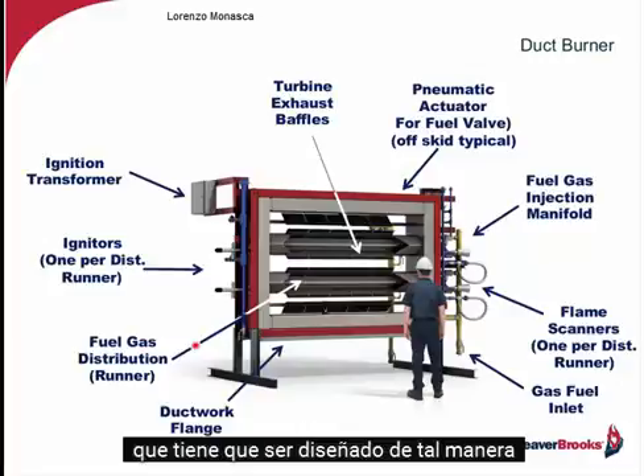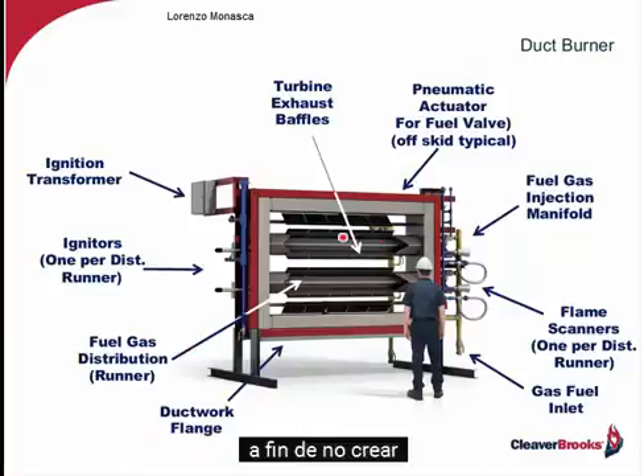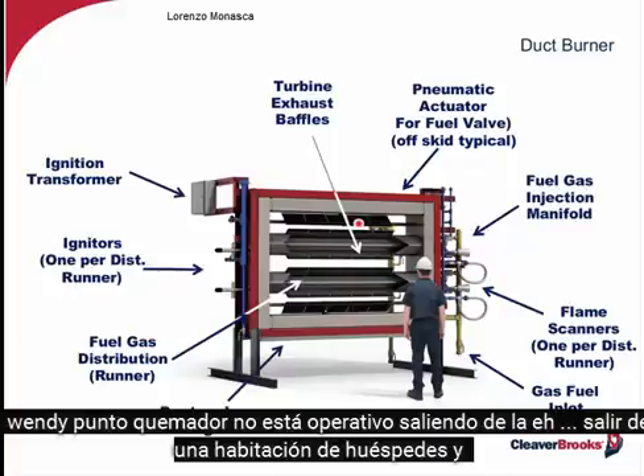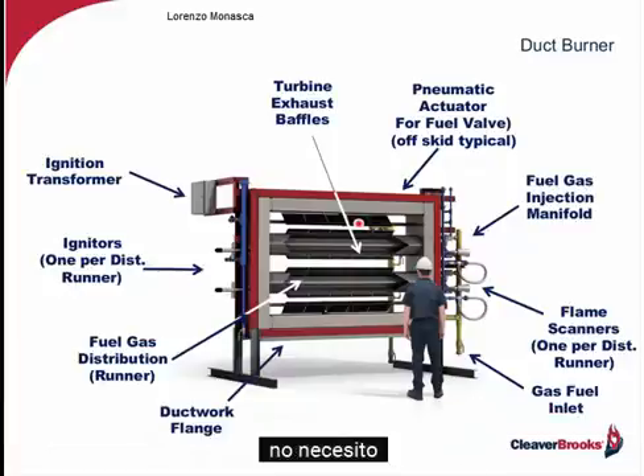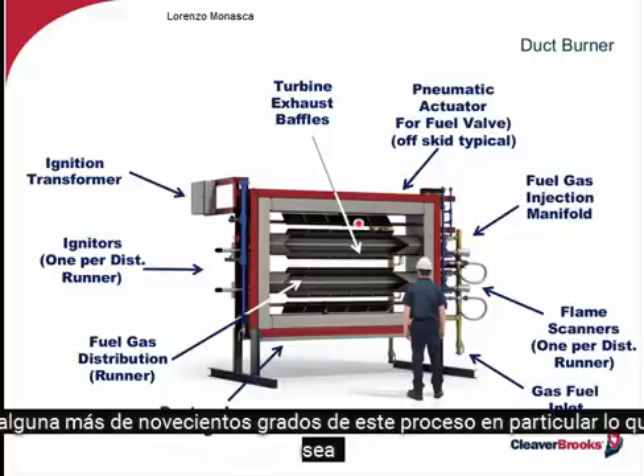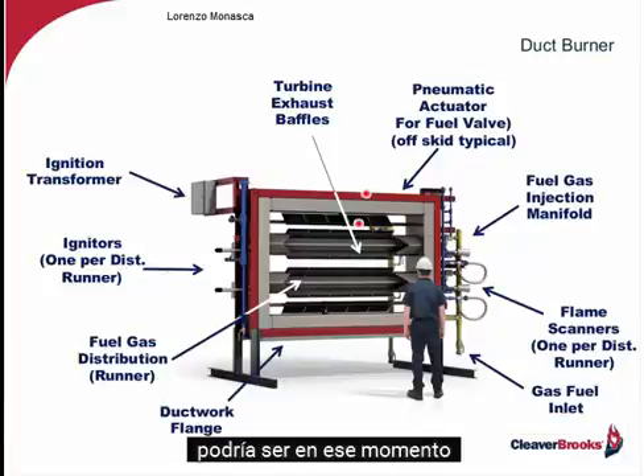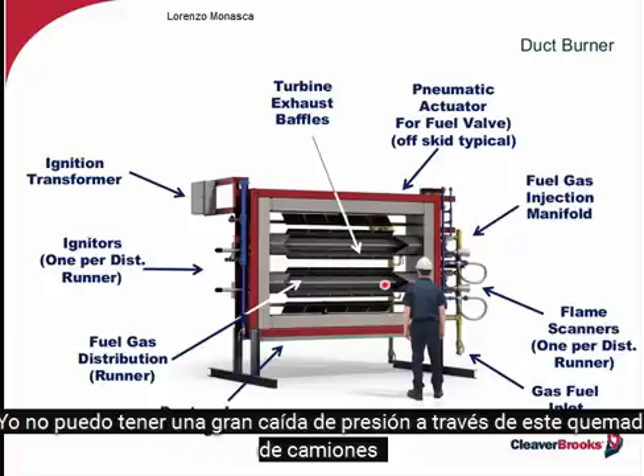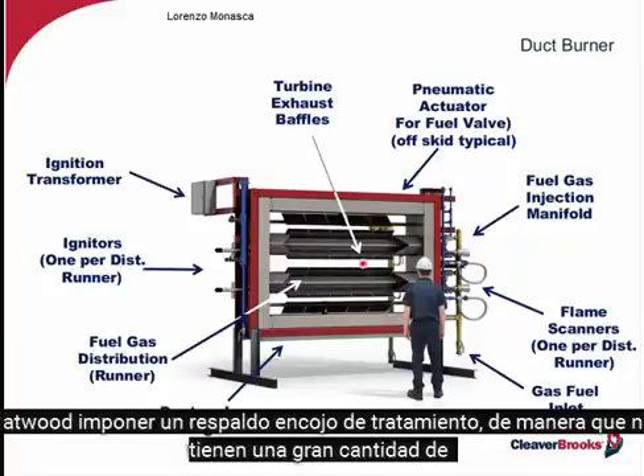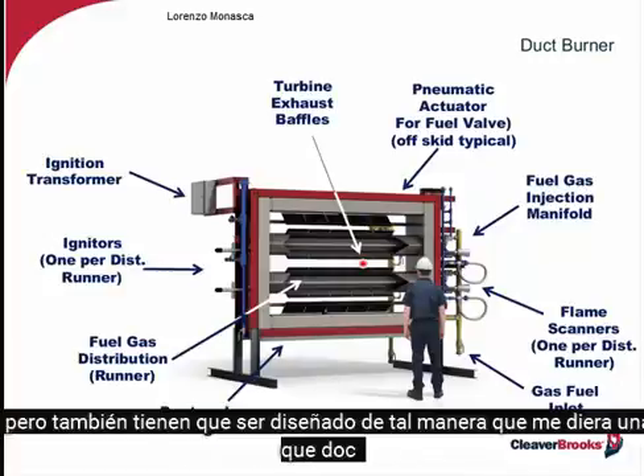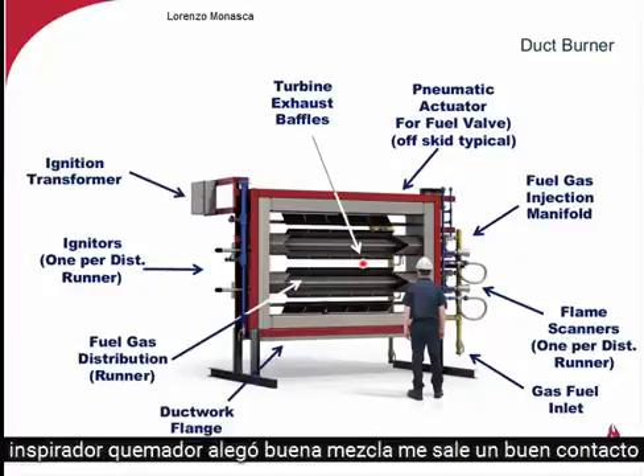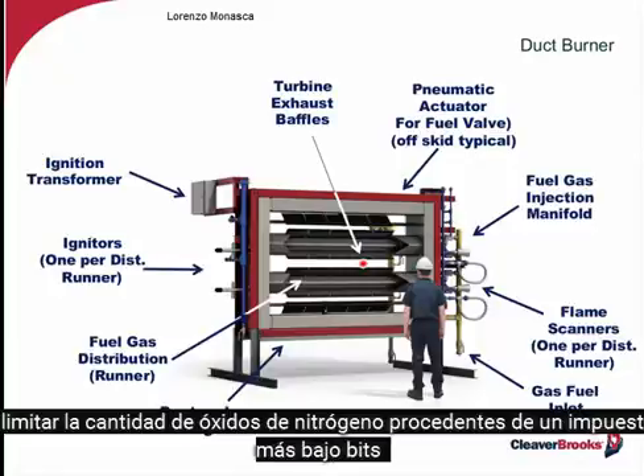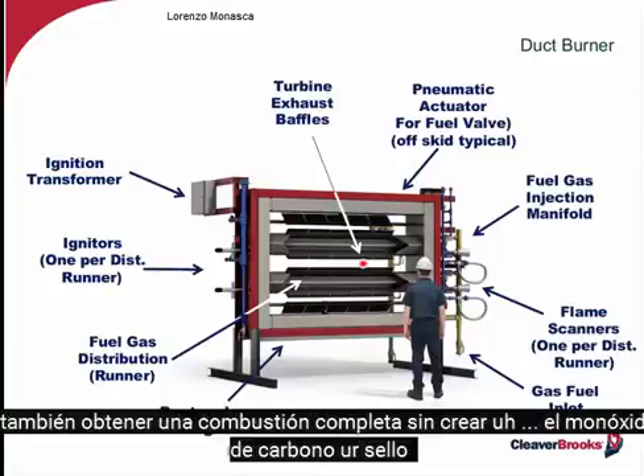Now, they've got to be designed in such a way so as not to create, when the duct burner is not operating, I'm coming out of the gas turbine, I don't need any more than 900 degrees for this particular process, whatever it might be at that point. I can't have a large pressure drop across this duct burner that would impose a back pressure on my turbine. So they've got to have a lot of open area. But they also have to be designed in such a way to give me, when that duct burner is firing, good mixing, good contact, so I can limit the amount of nitrogen oxides coming off of it, lower NOx, also get complete combustion without creating carbon monoxide or CO.